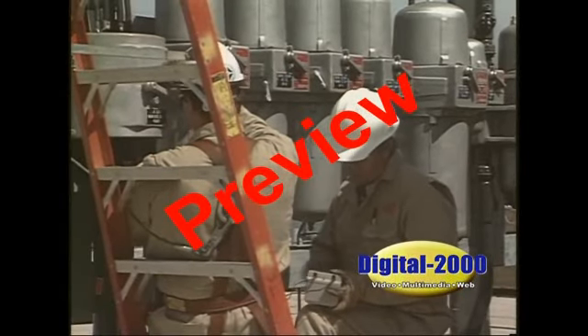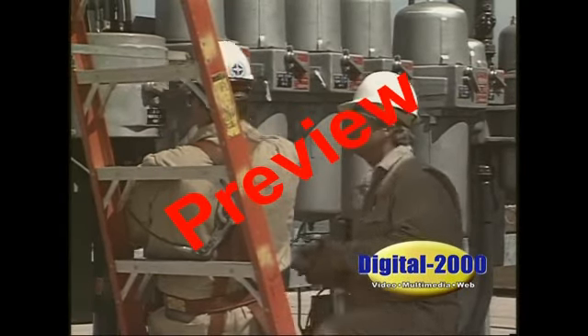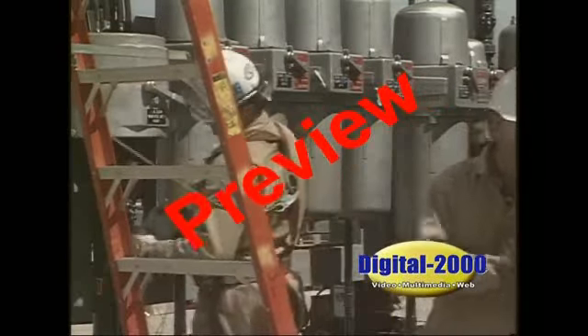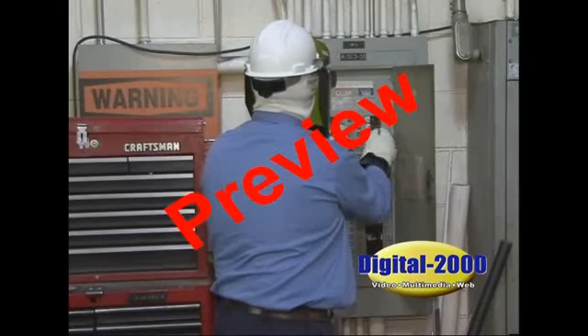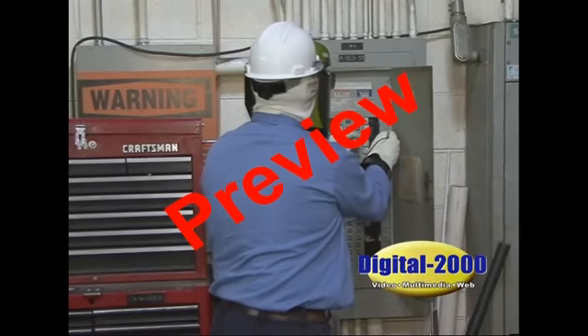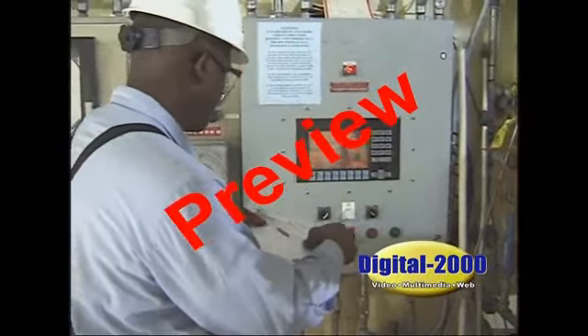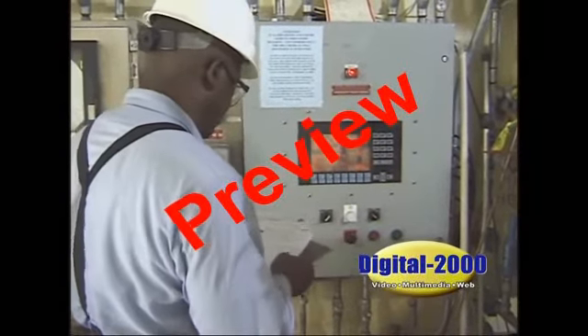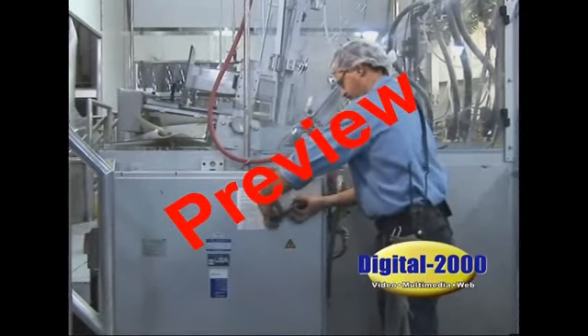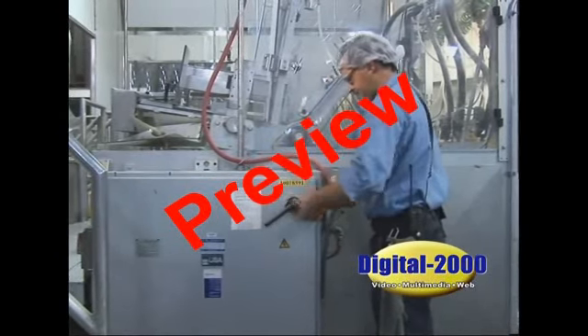Whether working with new equipment or older equipment, requirements of NFPA 70E and OSHA must be included, and coordination studies, short-circuit studies, and arc flash analysis must be developed. The more serious problem lies with older facilities which have not been upgraded and are still using older technology. Older design philosophies may result in longer short-circuit clearing times that can result in more serious injuries should an arc flash incident occur. Electrical safety is nothing new, nor is hazard assessment. It's just something that is required and must be done for safety.